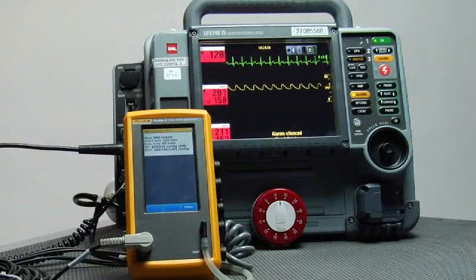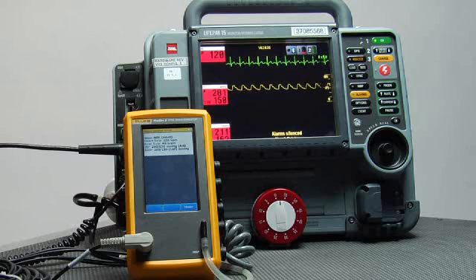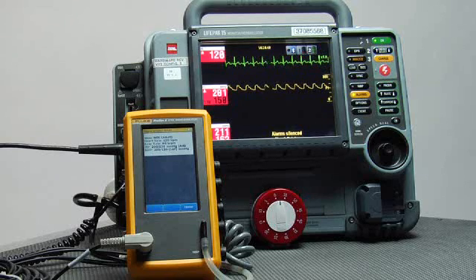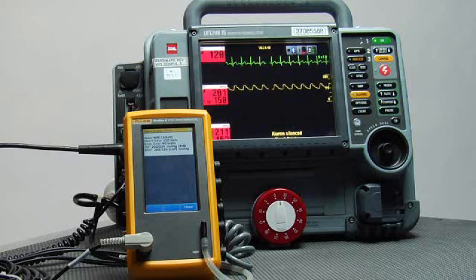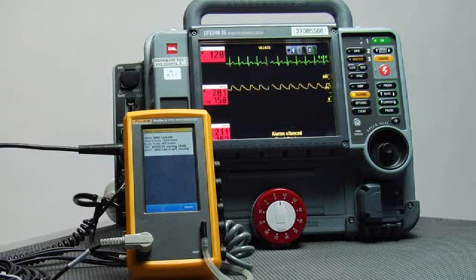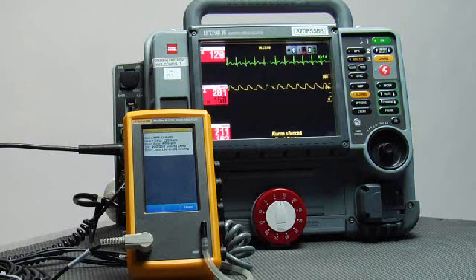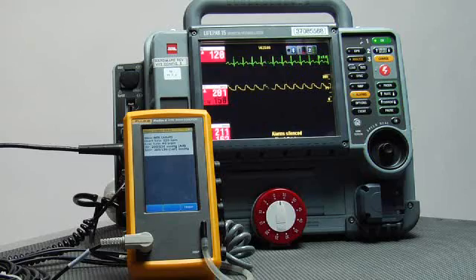We've seen audible and visual alarms. We've seen that the heart rate that we're simulating is exactly the heart rate being displayed. We see the ECG rhythm is the rhythm that we're sending. We see the invasive blood pressure channel that we're sending blood pressure information across shows the right values and a good waveform. We're seeing that the cuff blood pressure reading is exactly what we were simulating. And all the alarms and everything, this gives us a pretty good determination that there's nothing wrong with this patient monitor. The power of a simulator as simple as the little ProSim 4.